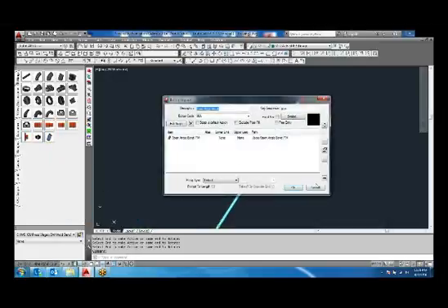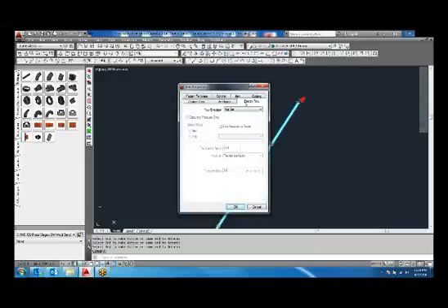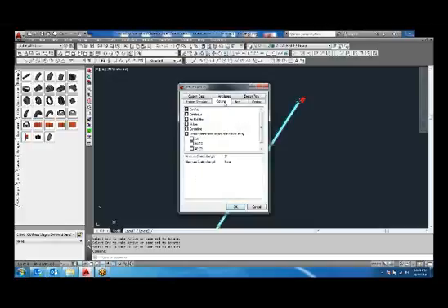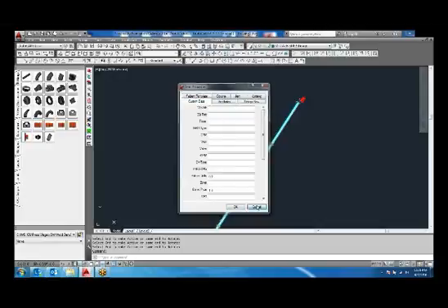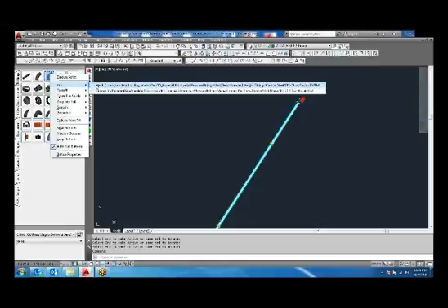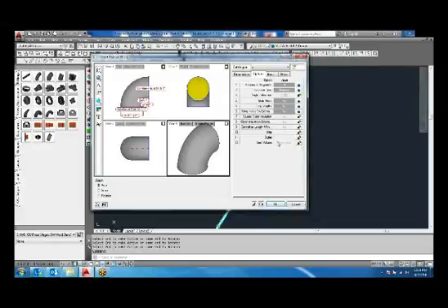I'll show you. Cancel that. I'll show you where that is. There's a tolerance in each fitting. All right. Let's see if I can find it here. Item. I don't know if this one will actually have it now that it's not managed. Let's actually look and see if these will show us. There's a plus or minus 3 degree tolerance in the angle. This won't have any because it's a weld.